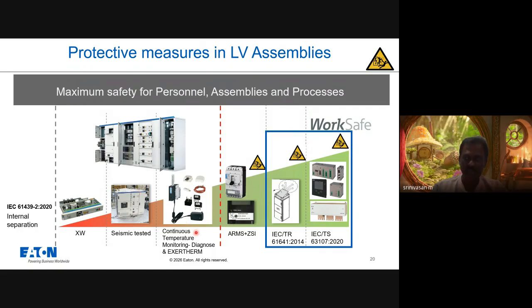We can go for temperature monitoring, which will be covered in the forthcoming slides of my presentation. We can also use an arc reduction maintenance system at the breaker level, and zone selective interlocking for better discrimination. If the switchgear is type tested for internal arc as per IEC 61641, that also improves safety. We can also talk about arc mitigation at the highest level. By mitigating the arc, we can still enhance protection to the entire system and to the operating personnel.